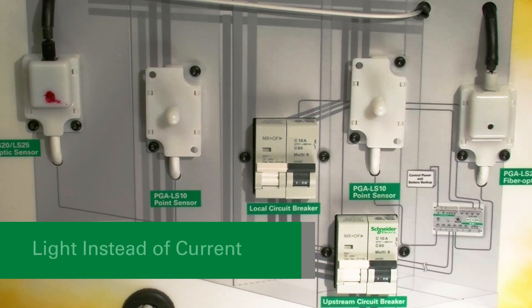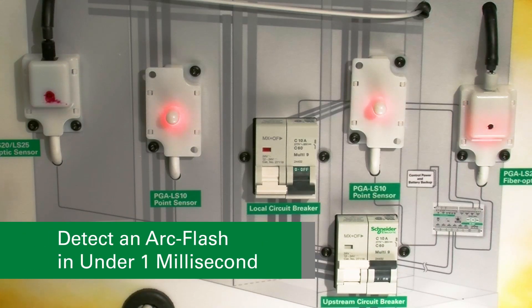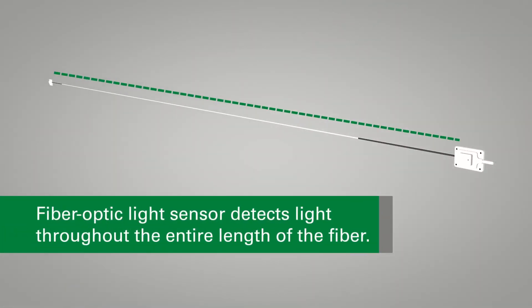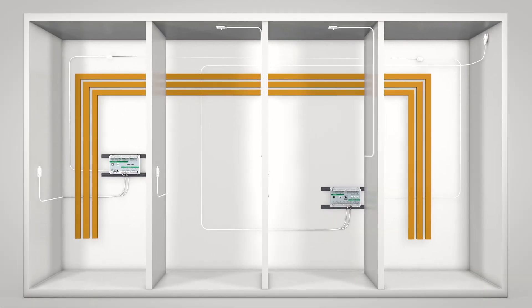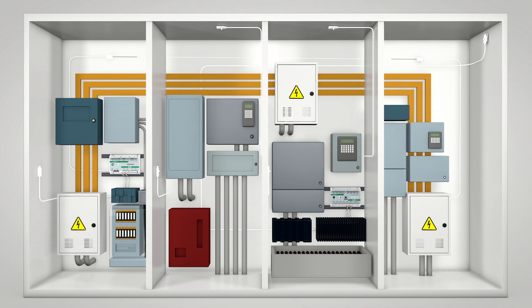Littelfuse ArcFlash relays use light instead of current to detect an ArcFlash in under one millisecond. The fiber-optic light sensor detects light throughout the entire length of the fiber. The sensor is ideal to protect bus bars, multiple compartment installations like motor control centers, or areas with many obstructions.